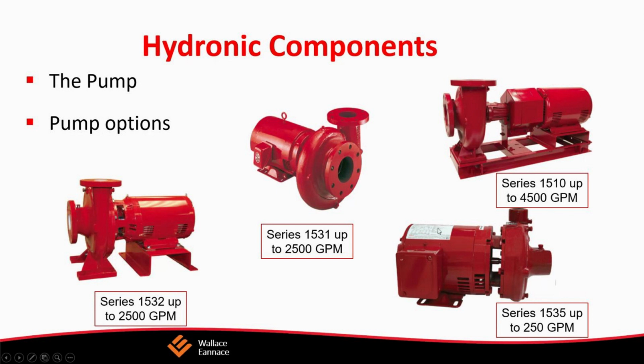There you have a dry motor, a rotor, seal, impeller, and bearing. These do not require annual lubrication, whereas the oil lubricated pumps need to be serviced and lubricated annually. And if you forget, they could wear out. These permanently lubricated pumps are a very good alternative to the older oil lubricated pumps.